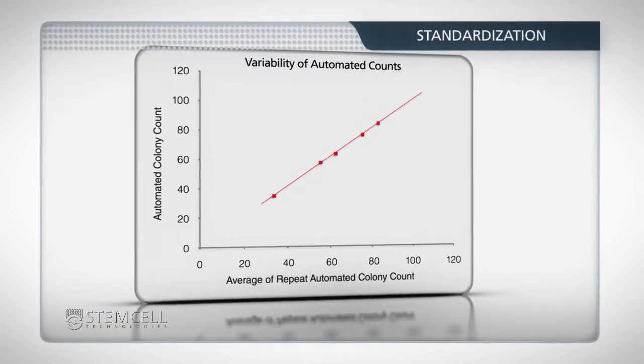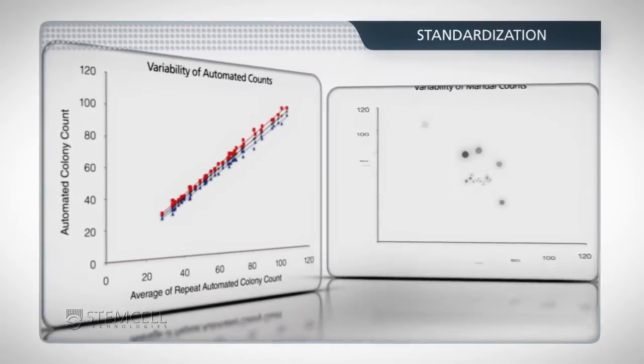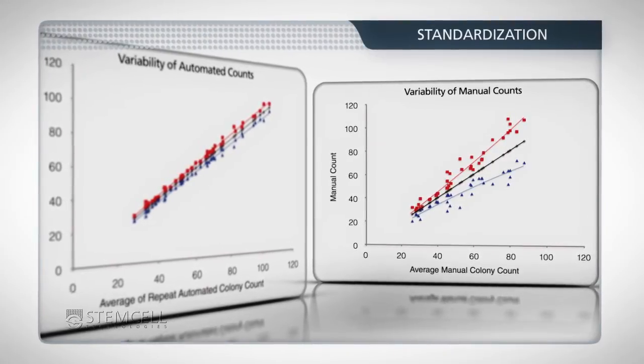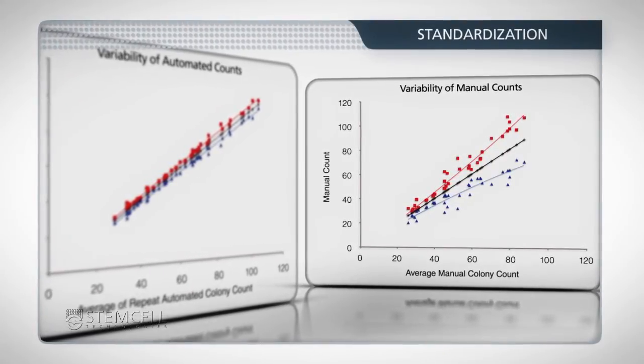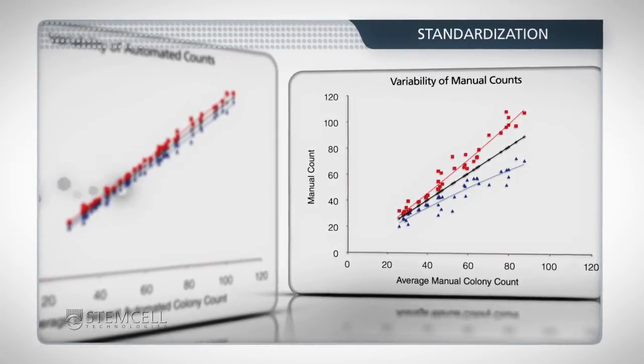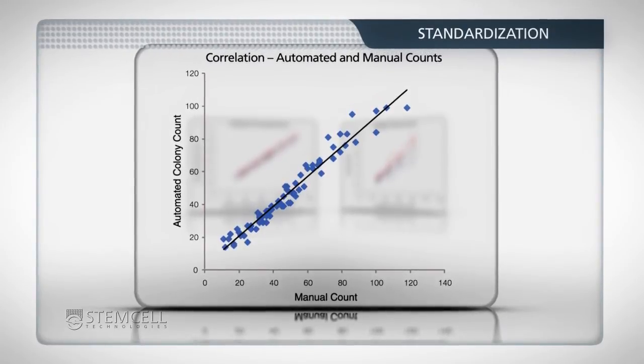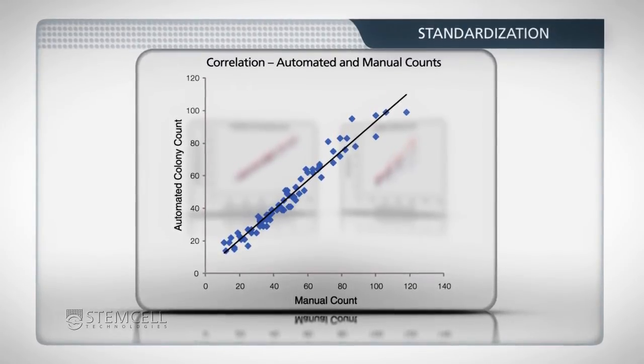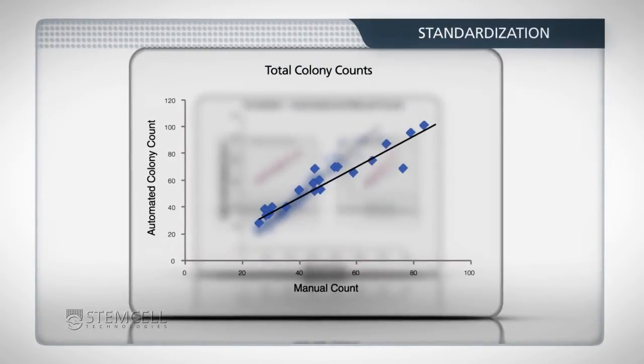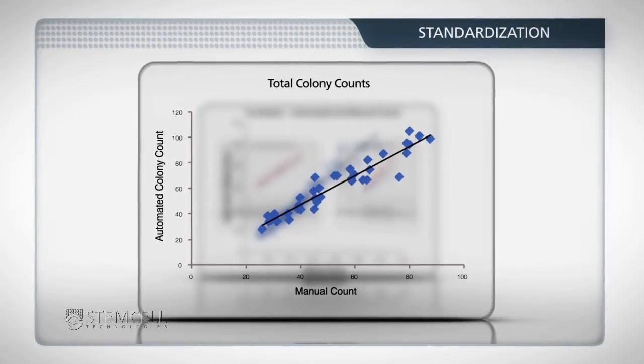Comparing the 95% confidence intervals of automated colony counts using StemVision and manual counts demonstrates the significant reduction in variability. Results from the CFC assay obtained using StemVision correlate strongly with manual counts. This graph shows the correlation between manual and automated counts for the 7-day assay using MethoCult Express. Similar results have been obtained for the 14-day assay using MethoCult H4034 Optimum.